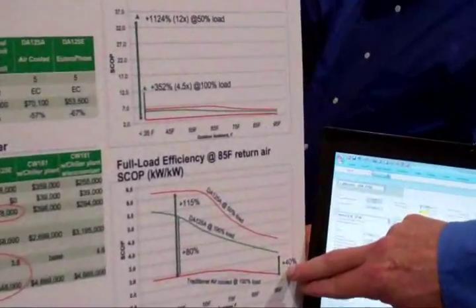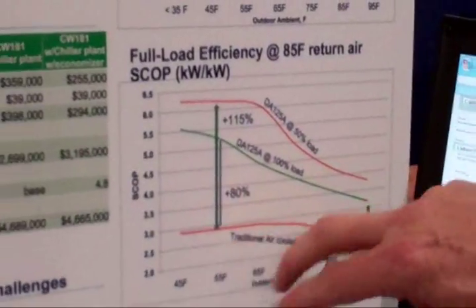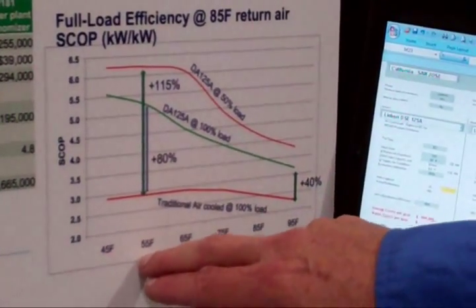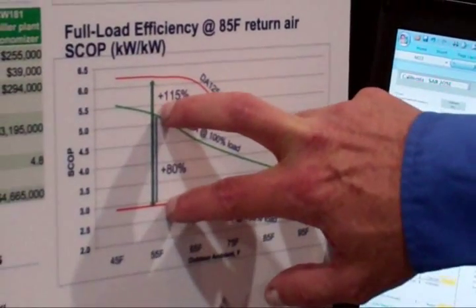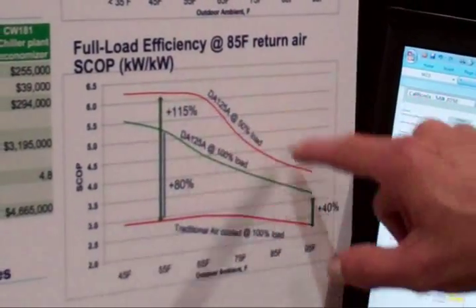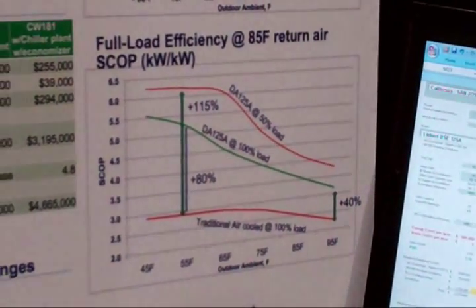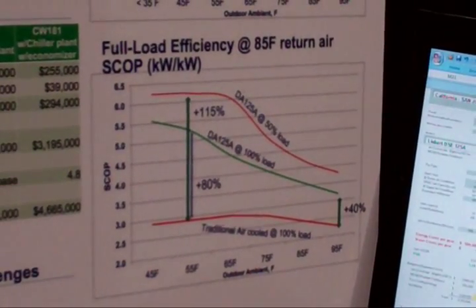What we're showing here is a comparison to traditional DX systems: at design day you're 40% more efficient. But as I move down to a lower ambient temperature outside — say 55 degrees — I'm 80% more efficient. If I go to part load, it's 115% more efficient. So you can really start taking advantage of cooler air, not necessarily just in winter, but at nighttime because it does cool off at night.